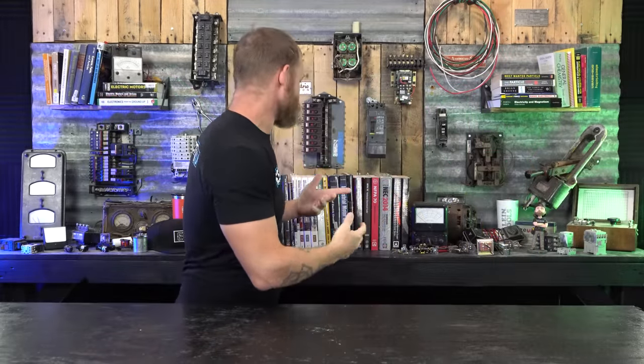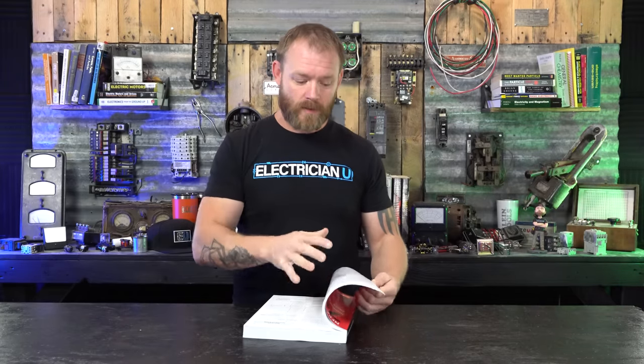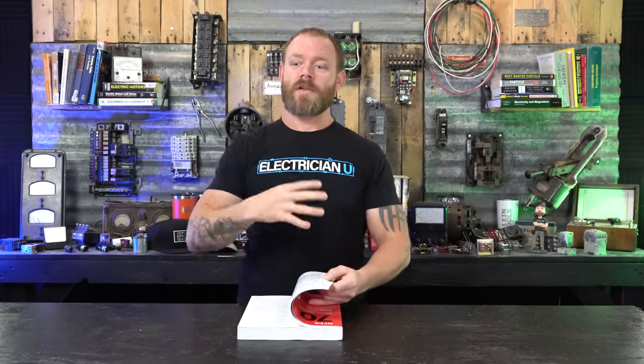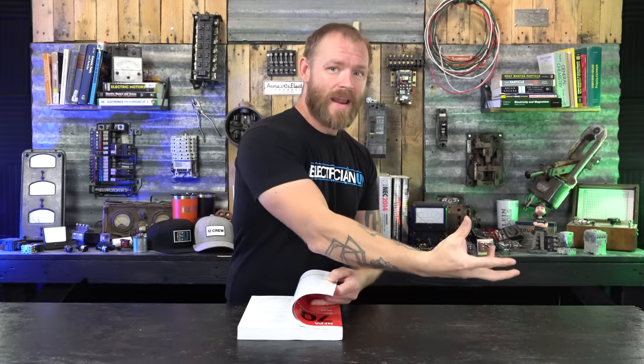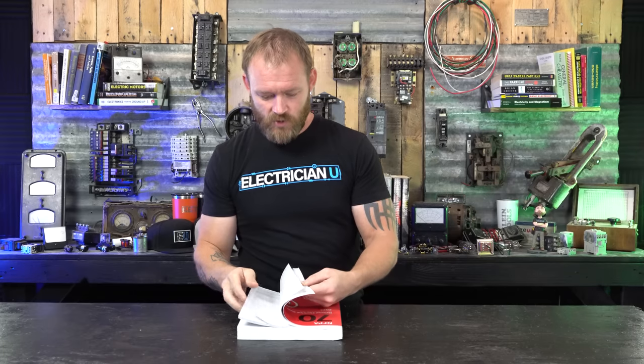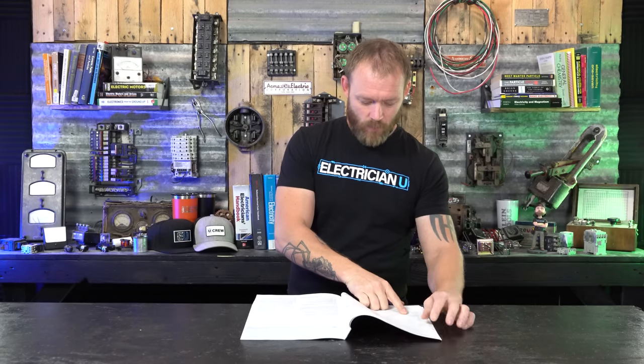What does code actually say about putting GFCI receptacles in? There are a lot of different parts of code and it depends on your environment. The NEC separates based on occupancy type — whether you're in a dwelling unit where people are living, versus somewhere like a bank conducting commerce. We're going to look at NEC 210.8: Ground Fault Circuit Interrupter Protection for Personnel.